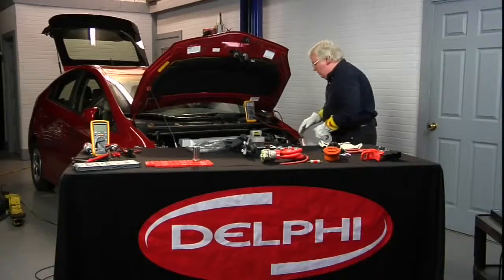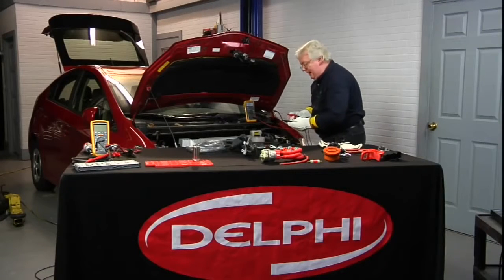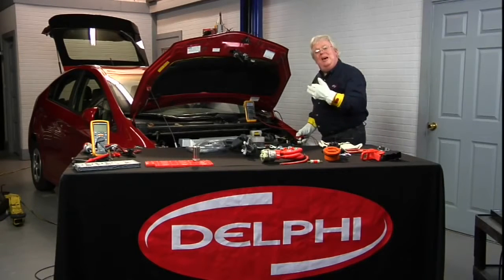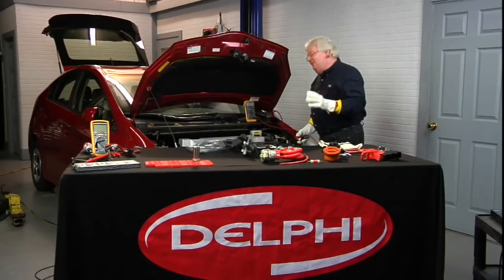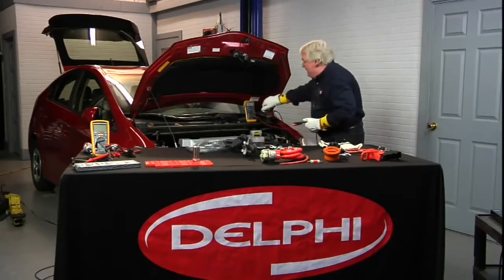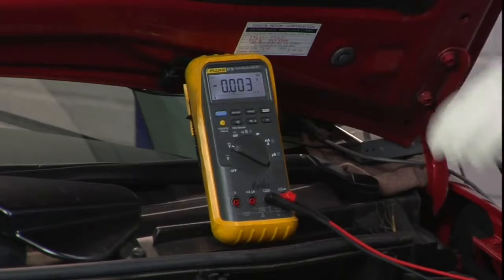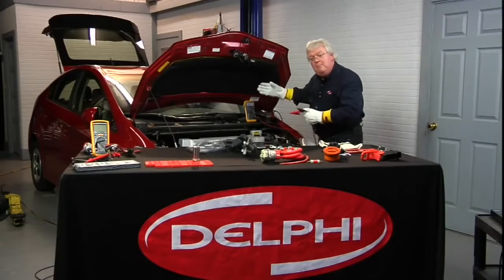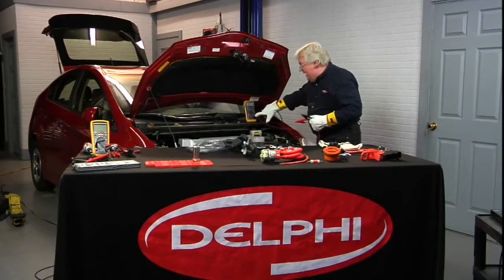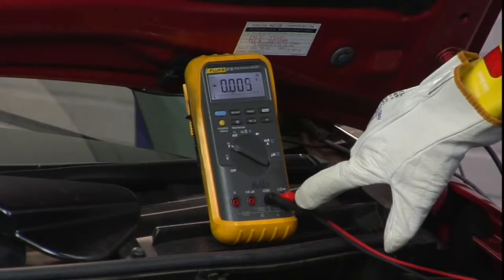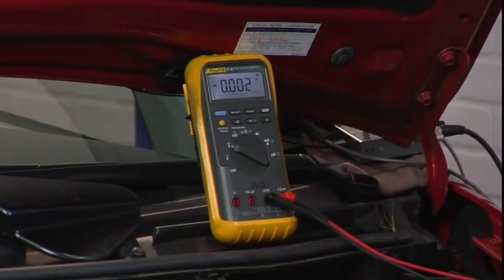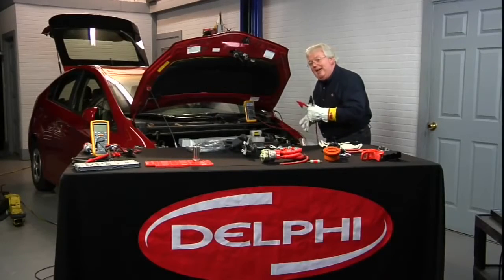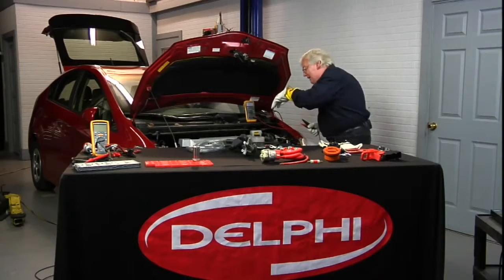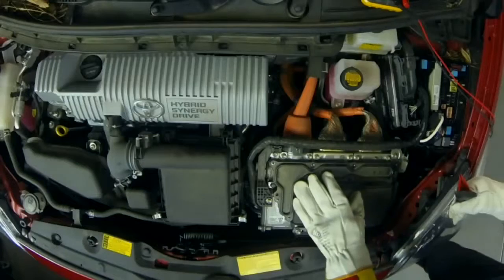Now we're going to check the meter to make sure it's working okay. I know that sounds kind of silly, but how many times have you accidentally had the meter in the wrong position? You had it on AC when you meant DC, or on ohms when you meant volts, or maybe you forgot you had it set up as an ammeter yesterday and had the leads in the wrong spot. We don't want to make a mistake like that and see 0 volts when we actually have high voltage underneath this cover.